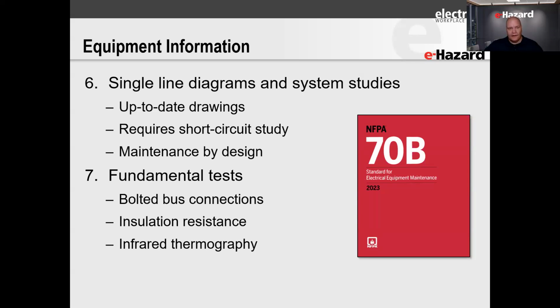You're going to see things like IR scans, bolted connection resistance tests, insulation resistance tests. Those are basically universal across the board. If you think about it, if you were just doing these basic things from a maintenance standpoint, it's already going to put you leaps and bounds above where we were at.